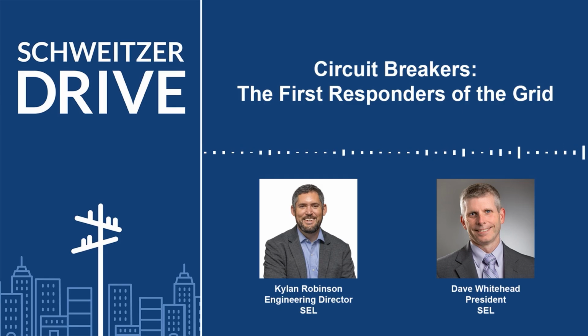Waiting for a zero crossing is what really drives that 2 to 3 cycle limit. So we have to look at other ways, not waiting for a zero crossing, to make it faster. And as I was saying before, DC circuit breakers don't have that zero crossing. And so we already have to do things like use commutation circuits, maybe use hybrid or solid state devices in order to make that trip go faster, right? So a hybrid device will use a solid state commutation circuit to offload some of the energy while you open up the mechanical trip contacts. And that can get you down to about the low single-digit milliseconds for a clearing time. A true solid-state breaker can operate in 10 microseconds or so. And so that's really phenomenal, orders of magnitude better than what we're seeing today.